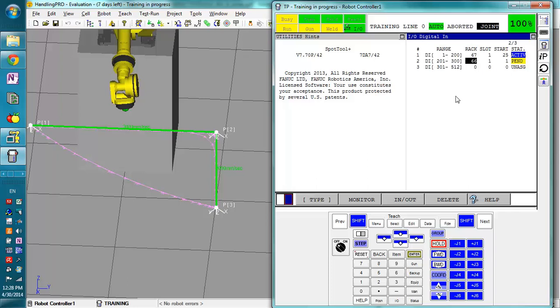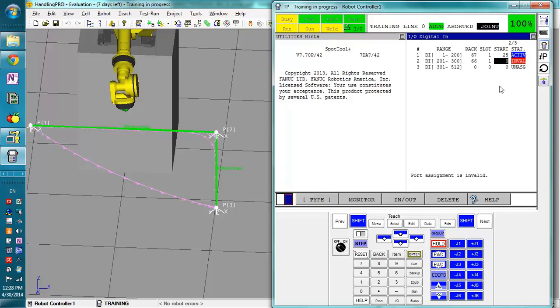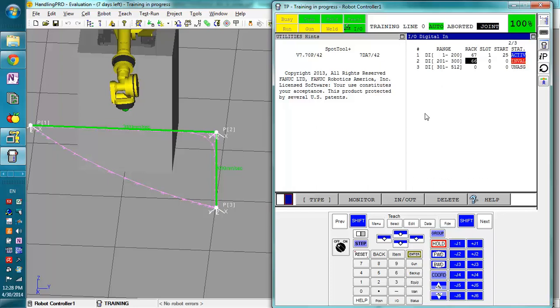When you're dealing with the PLC side, 1 will be byte 0 and then 8, no, 9 will be byte 1 and so on and so forth. You do not start these at 0 as you would in some PLCs. It must start at a 1. So I'm going to actually delete this because I don't really want that in there.